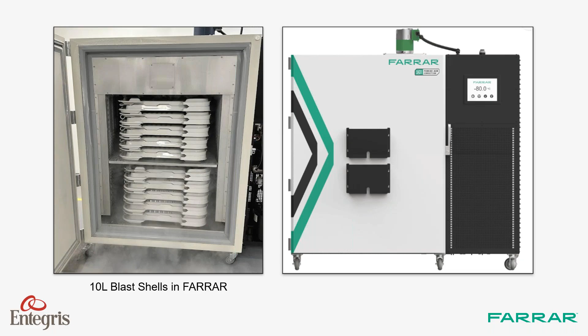So I wanted to introduce the model 4000 control rate chamber from FARRAR and give a short overview on it. When you're freezing materials, even small batches, it's important that you are using equipment with sufficient cooling capacity. You might ask why. With 2 easy reasons. One, you want it frozen fairly fast. Your yields and processes probably cannot afford to wait for a slow freezing process, typically found when you're using a ULT. And 2, putting excess heat load into the chamber will overwork a compressor set, leading to premature failures if it's not designed to handle that extra load, even for the best high quality units on the market.